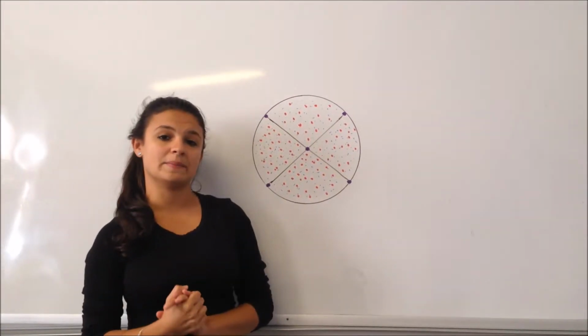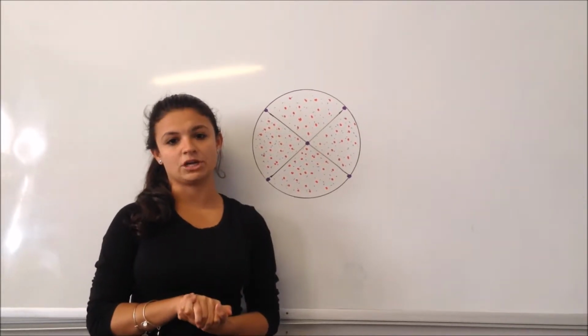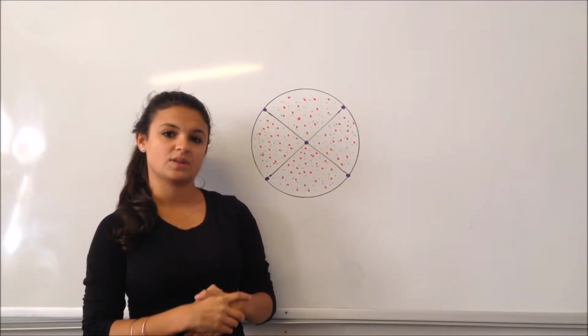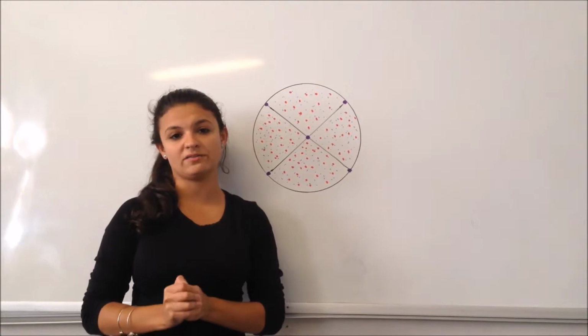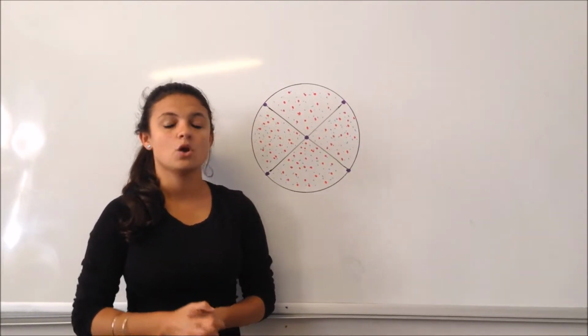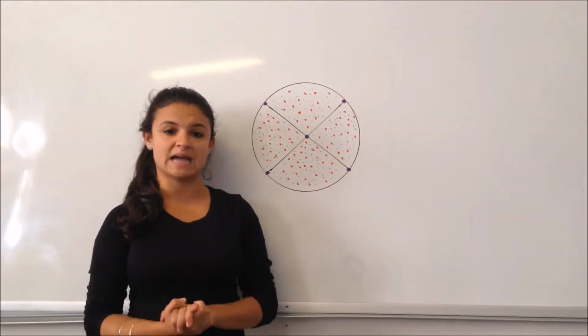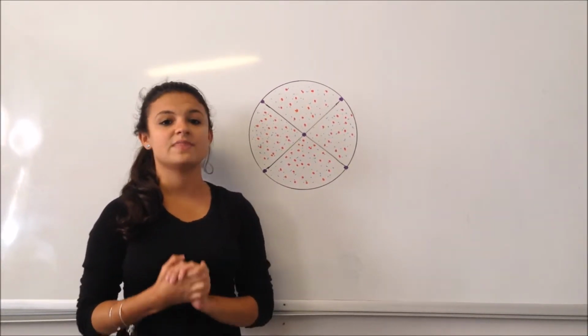The thermocouple element senses temperature. We heat the wire and measure its temperature as the surrounding gas cools the thermocouple. Because the temperature of the wire is inversely proportional to the amount of gas in the tube, we can infer pressure in the system.